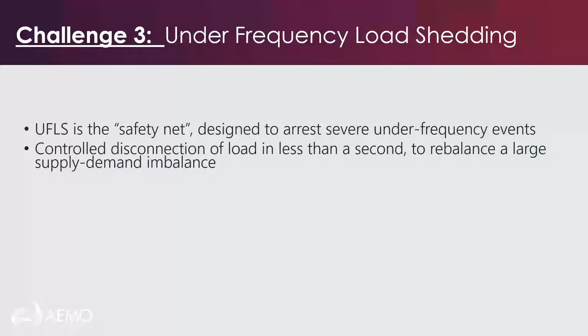If we see a bunch of generation trip, the frequency will drop very quickly, and when it falls below 49 Hertz, that under-frequency relay, the many relays in the grid will detect that and will open the circuits to disconnect those loads. That drops a bunch of load off the network and hopefully will arrest the frequency decline and assist with restoring it back to 50.